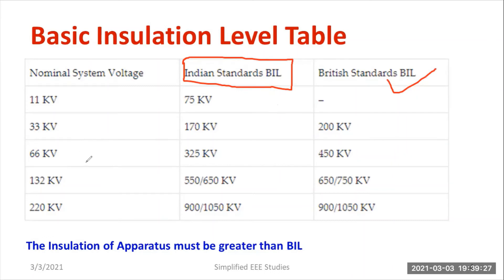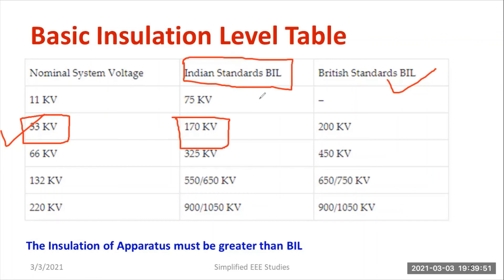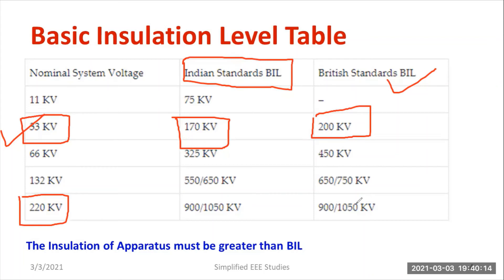Let us make a comparison. Suppose you are operating a system at 33 kV nominal system voltage. If I consider Indian Standards BIL, I would design the insulation for a dielectric strength of 170 kV. If I consider British Standard BIL, I would provide a dielectric strength of 200 kV — that is the difference. In the case of a 220 kV system, both the Indian and British standards are identical: the insulation is maintained at 900 to 1050 kV in both cases.